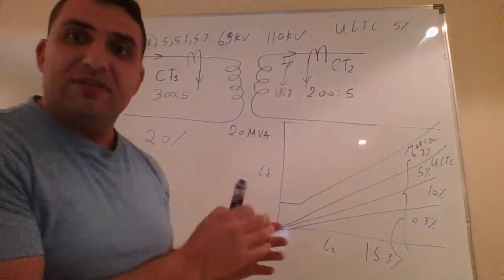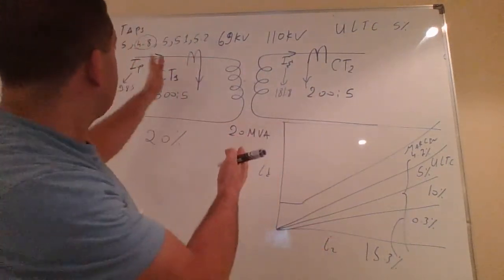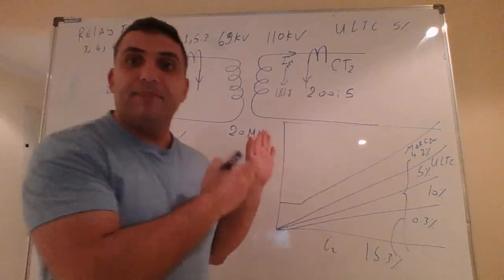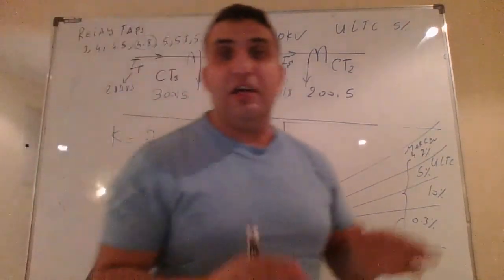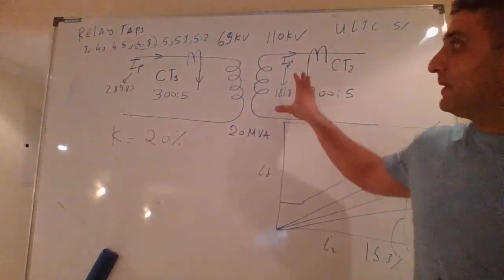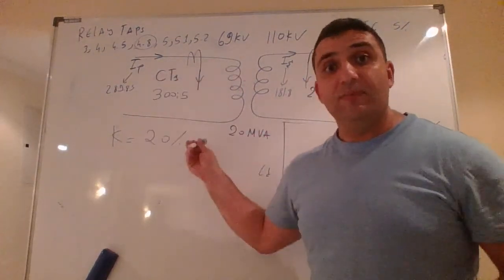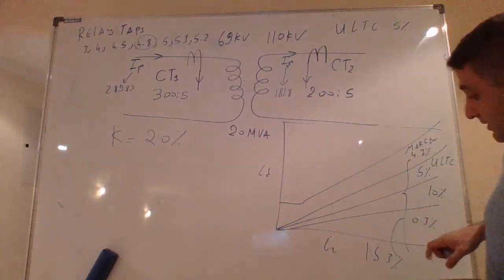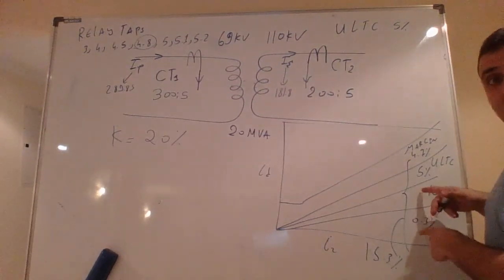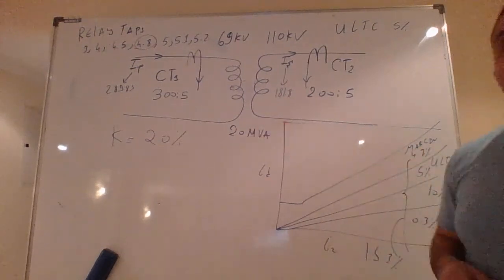In the previous lecture, we discussed the element, what the differential ID is, what IR is, and so on. In this, I'm hoping that this example gave you enough information regarding determination of the CT ratio and then determination of the actual CT mismatch error, CT error, which we've already done before, ULTC and the margin, and how to specify.